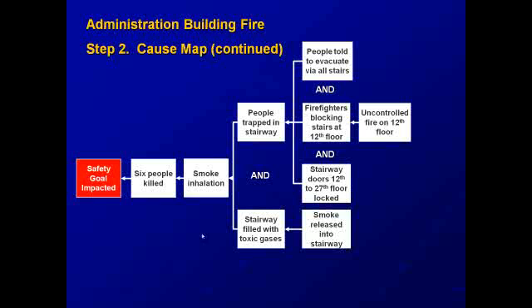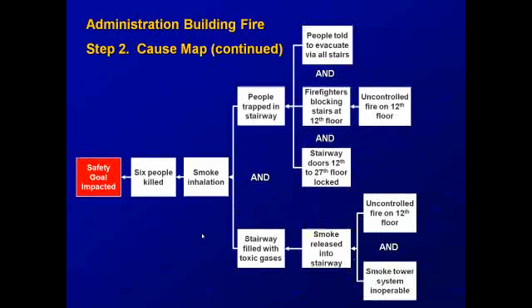The stairway was filled with toxic gases because smoke was released into the stairway due to the uncontrolled fire on the 12th floor, and because the smoke tower system, which would have removed smoke from the stairway, was inoperable.